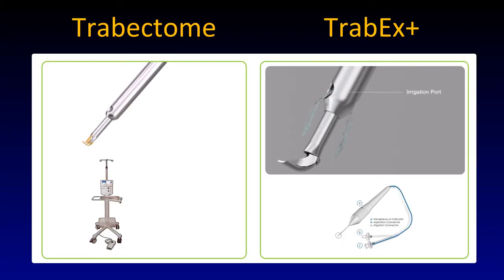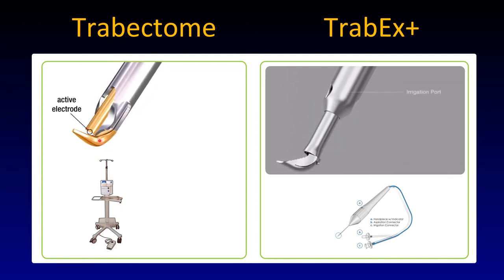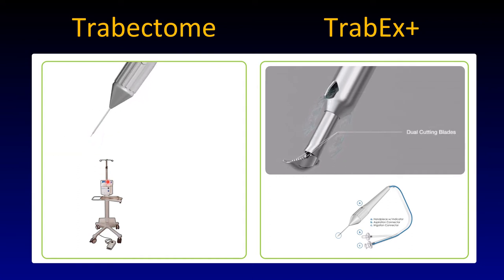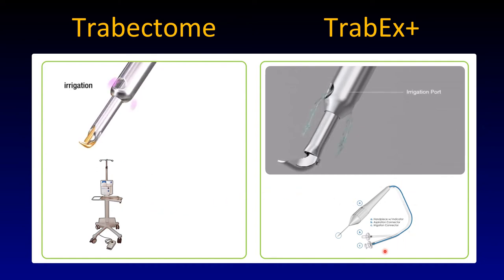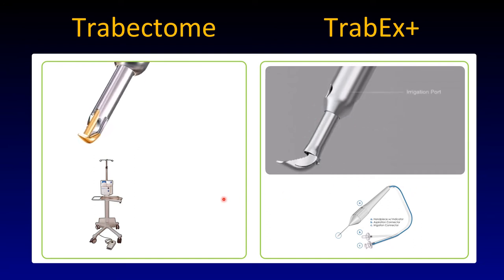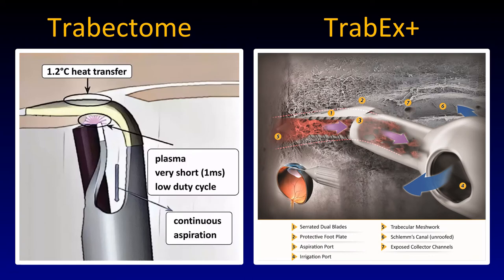Technology and techniques. On the left you see the Trabectome: irrigation, aspiration, and two electrodes that create a micro-lightning discharge, creating plasma that molecularizes the trabecular meshwork. It's not cautery — often misrepresented. It's more like a YAG laser where the tissue is disrupted. Here is the generator required, so there are overhead costs. Not so with the TrabEx+ — you can plug it into a phaco machine or any other aspiration device. The TrabEx+ has active irrigation-aspiration. Here you see the dual blade, which is serrated in the case of the TrabEx+ to initiate a cut more reliably.